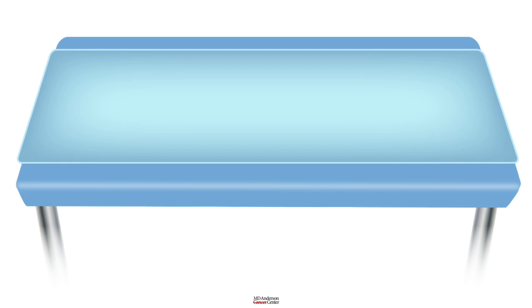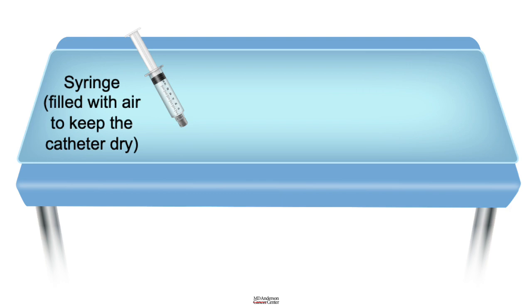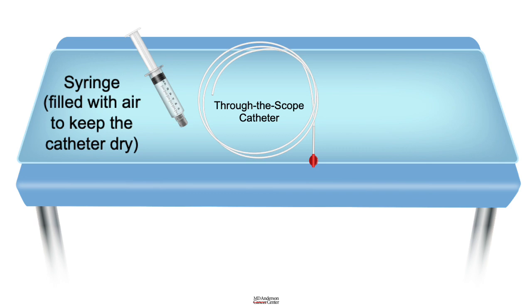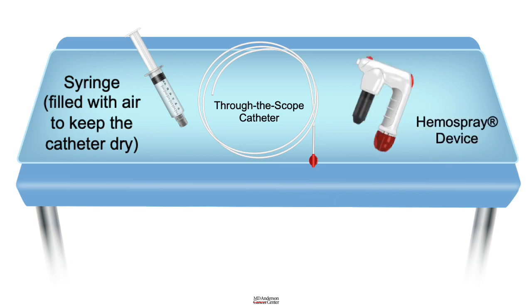When it comes to setting it up, you need a large bore syringe filled with air to flush the catheter as it's being delivered down the endoscopy channel to keep the catheter dry. It has to be dry, otherwise the powder will clog the catheter. So it's very important to do this maneuver, and that is keep on flushing that catheter. This is the through the scope catheter, and keep it dry. Then you have the Hemospray device that actually is powered by a carbon dioxide cylinder that delivers a special powder that tends to form a coagulum and clot off the blood vessels.